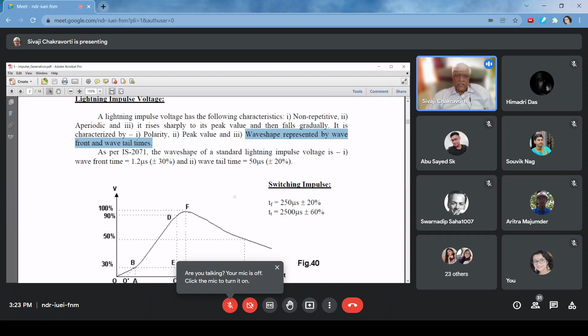As per IS 2071, our Indian standard, the wave shape of a standard lightning impulse voltage has a wave front time of 1.2 microseconds, but there will always be a tolerance of plus minus 30%. What is this wave front time? That is the time required to reach the peak.